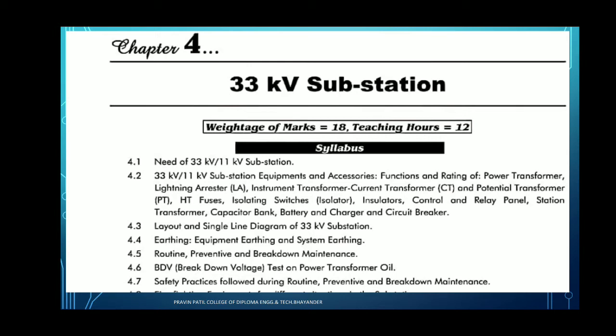Then we have to see the function and rating capacity of each and every equipment: power transformer, lightning arrestor, instrument transformer, current transformer and potential transformer, which are required in a 33 by 11 kV substation, HT fuse, isolating switches, that is the isolator, insulators, control and relay panel. Then substation transformer, capacitor bank, battery and battery chargers, as well as circuit breaker. So these are the main components which are required in a 33 kV substation.